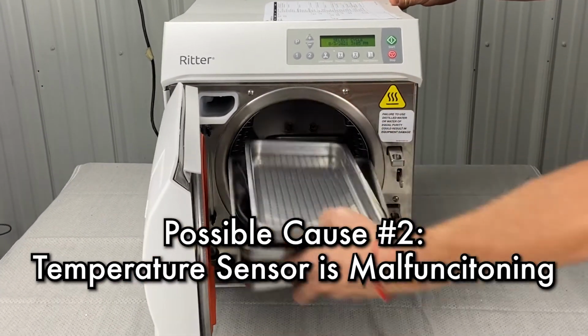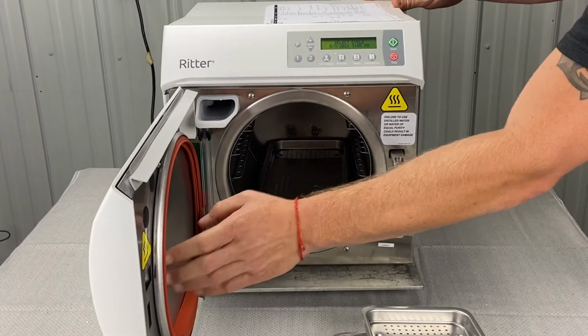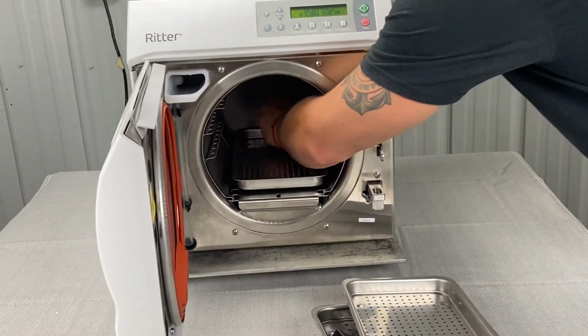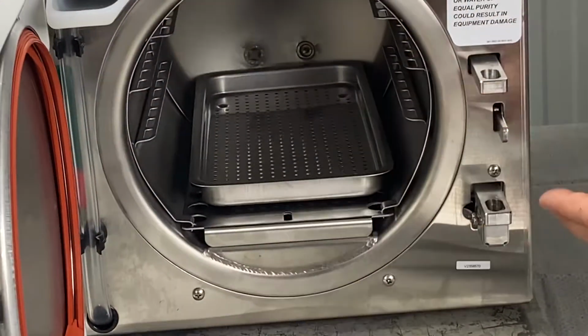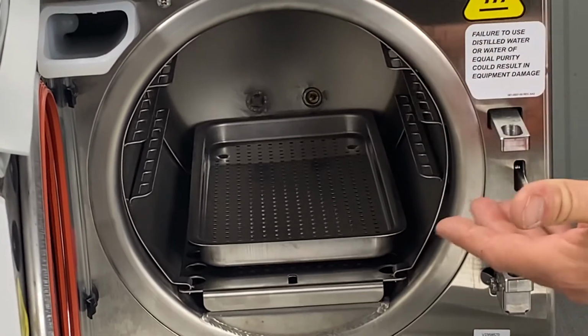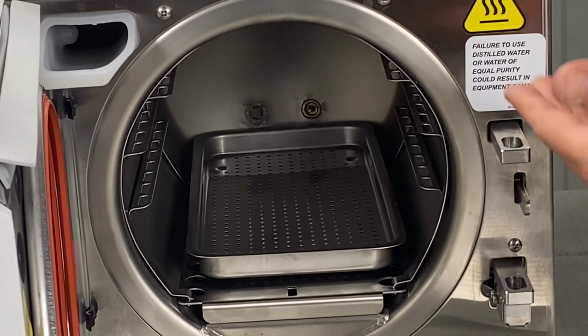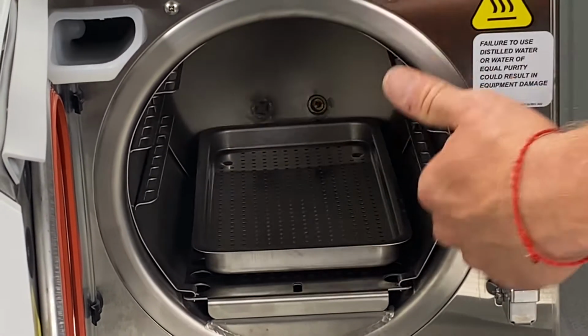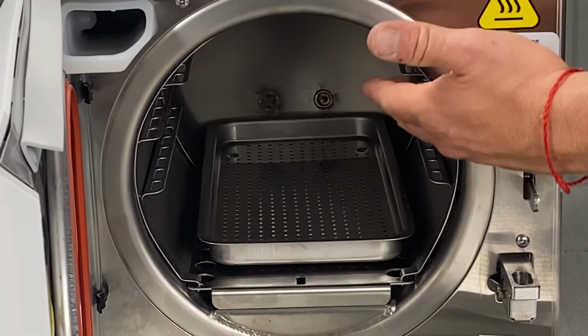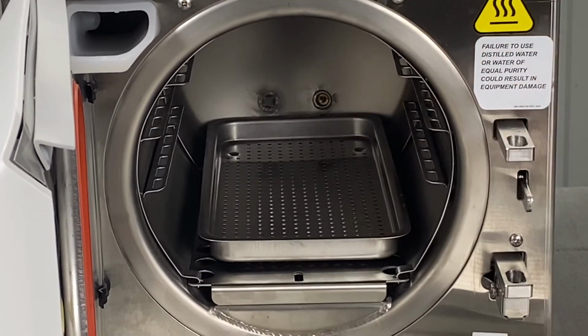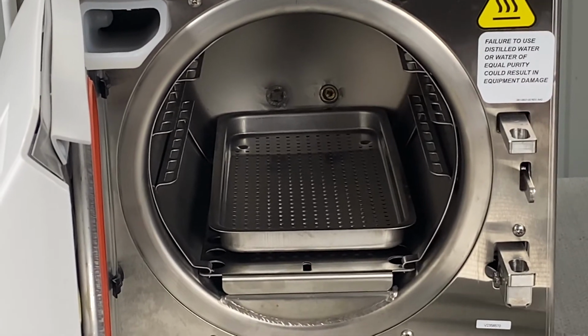Temp sensor is back in here. It's way in the back here. Make sure it's not crowded. Make sure nothing's leaning on it. Make sure it's not dirty. We have speed clean. You can run a couple speed clean cycles. You get an abrasive pad. You scrub that off with some distilled water and an abrasive pad.